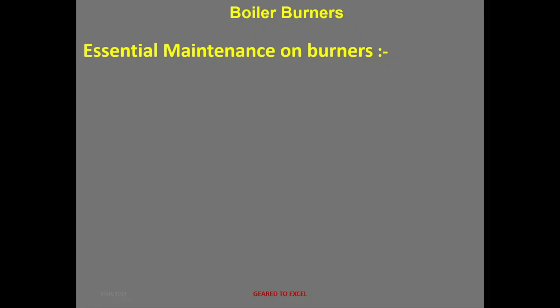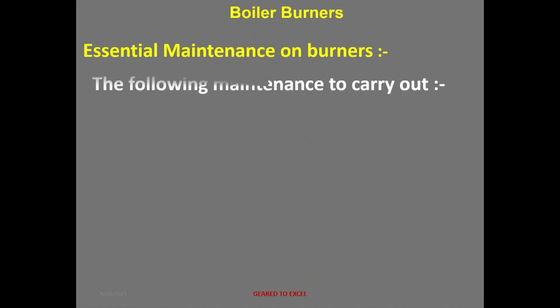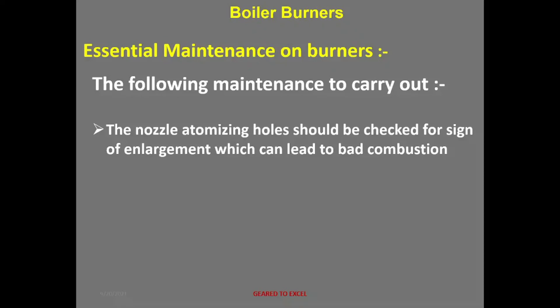Essential maintenance on burners: the nozzle atomizing holes should be checked for signs of enlargement, which can lead to bad combustion. The swirl plate should be inspected for erosion and corrosion. The ignition electrode clearance should be checked for efficient flame establishment during startup.